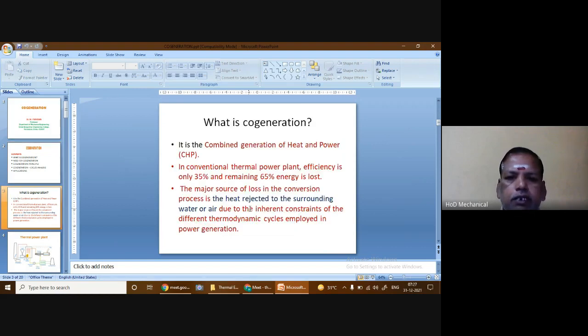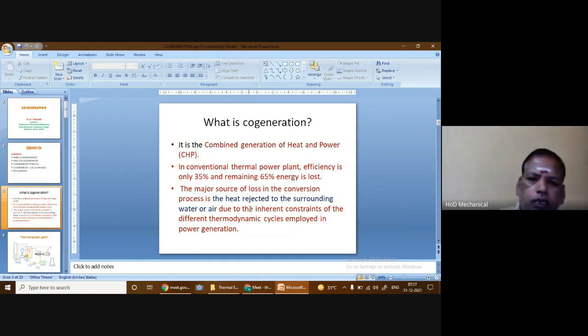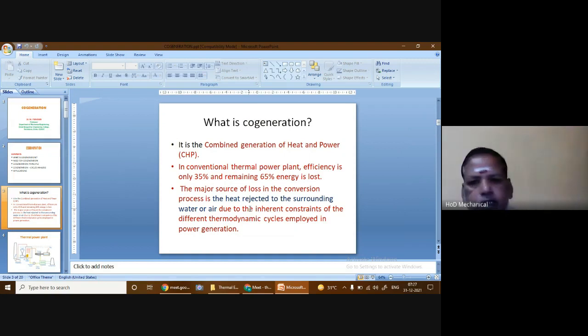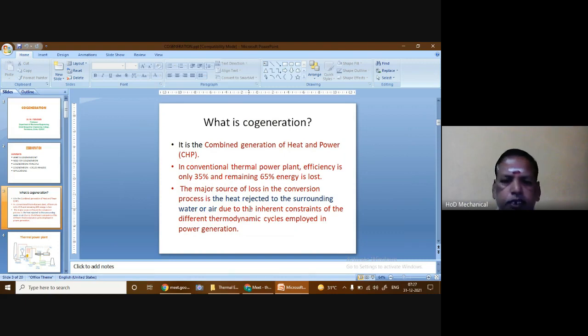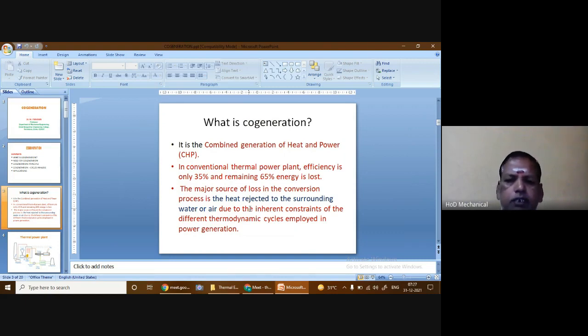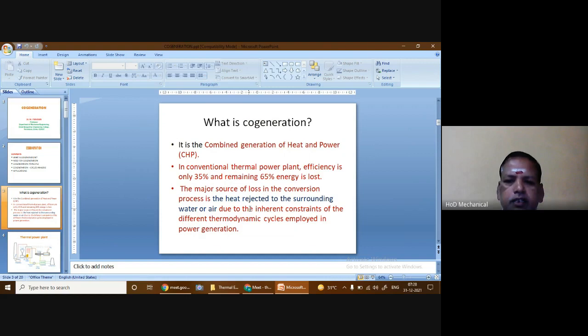What is cogeneration? It is the combined generation of heat and power. In a conventional thermal power plant, the efficiency is only 35% and the remaining 65% of energy is lost. The major source of loss in the conversion process is the heat rejected to the surrounding water or air, due to the inherent constraints of the different thermodynamic cycles employed in power generation.